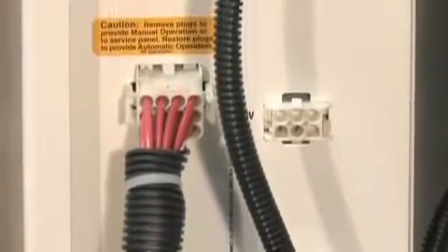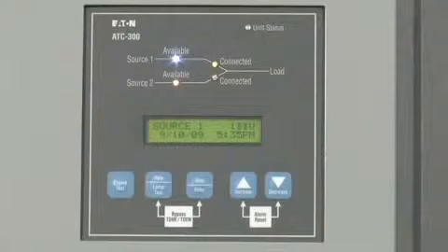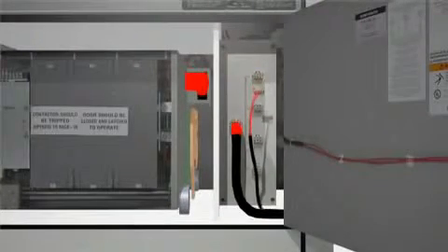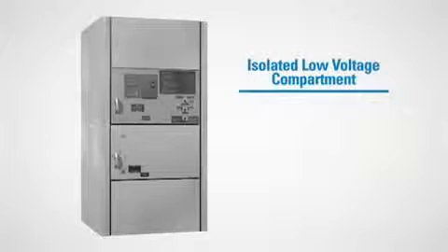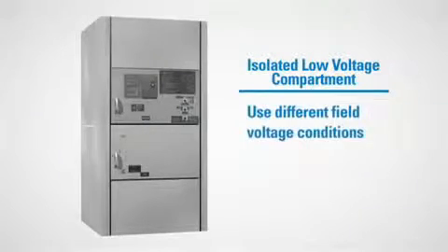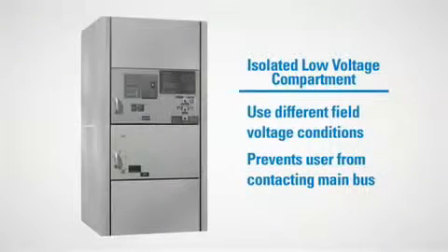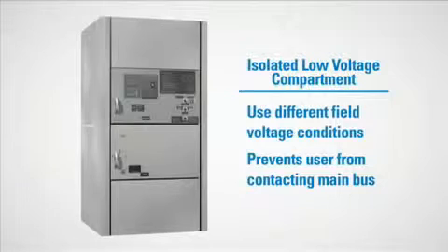This transformer allows the user to change the incoming voltage setting simply by reprogramming the voltage in the microprocessor controller and moving the plug to the proper voltage. This design not only allows the ATS to be used with different field voltage conditions, but also prevents a user from inadvertently contacting the main bus during maintenance.